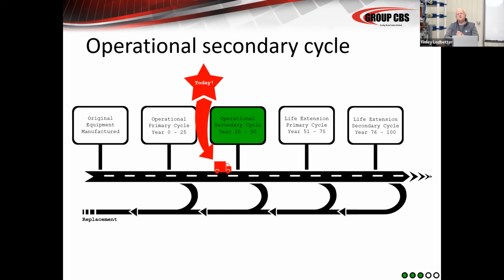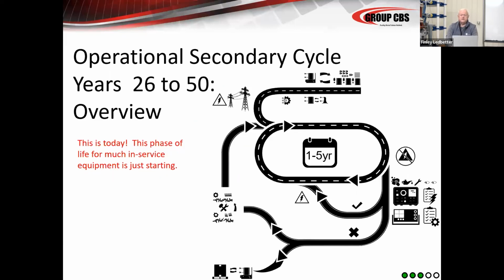So you need to do some debriefing, and that's tough to get done. So be careful here because you have spare parts, you have maintenance tools, you have specific test equipment that came with the switchgear, you have transport trucks and lift trucks and things that came with the switchgear, you have spares, you have all these things for the switchgear. And if that intelligence, if that information doesn't pass down from one generation of maintenance crew to the next, you lose a lot of the utility of your switchgear. You'll end up buying equipment parts and things you already have at a later date. So in the next life cycle, you're going to go right back into the secondary life cycle so that you're going to run it again for 25 years.